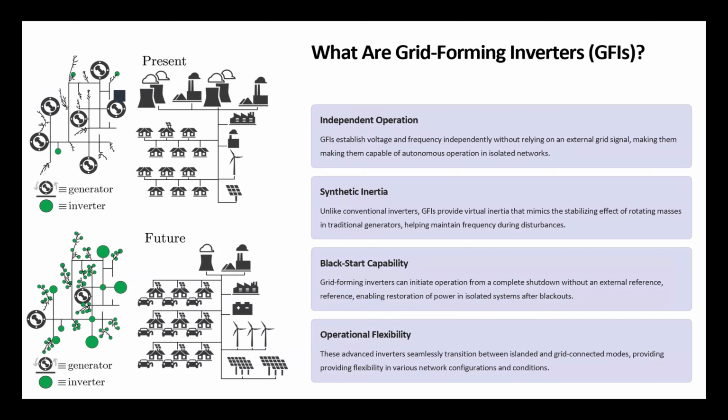When the generation or the load varies, the rotor's inertia allows them to keep rotating, thus ensuring true grid stability. With renewable energy sources, it's way different. Their generating units do not have large rotating masses. They're connected to the grid by power electronics. Power electronics devices work rather like a musician who would read his score before joining the orchestra. So he only follows the conductor, namely the grid frequency. The devices observe the grid frequency in order to inject their power. Therefore, they don't offer any natural inertia, so-called spinning reserve, that would help ensuring system stability.